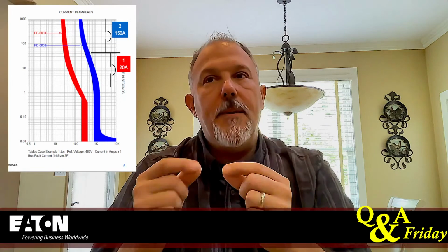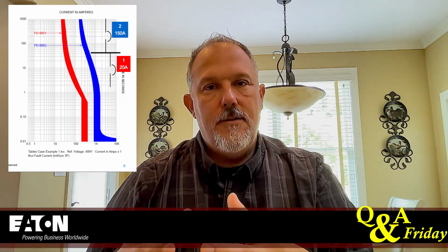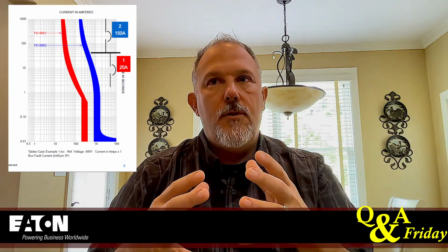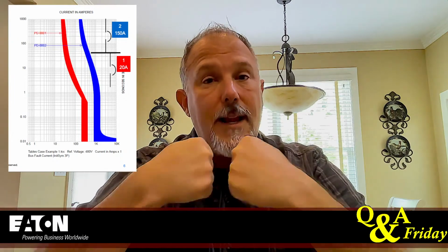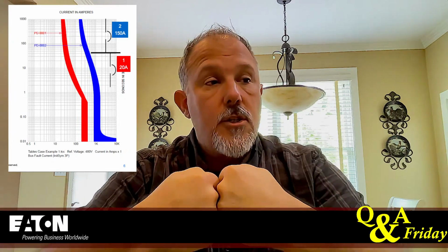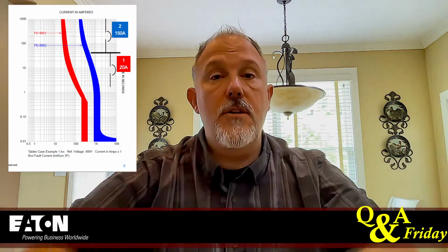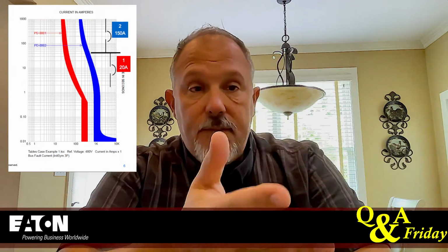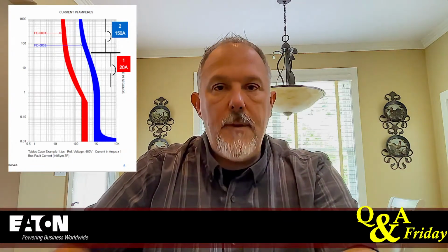So what happens is everything gets beefier, right? Meanwhile, the breaker's getting bigger because I've got to hold those contacts closed. And I don't want chatter. I don't want dimples. I now have 5,000 amps, not 1,000 amps or 800 amps, that I've got to hold these contacts closed for. So I need to bring more beef, and that makes the circuit breaker larger. So instead of, say, a 150 amp device, I might have to go to a 400 amp frame and dial it down, if I can get it to 150 amps.